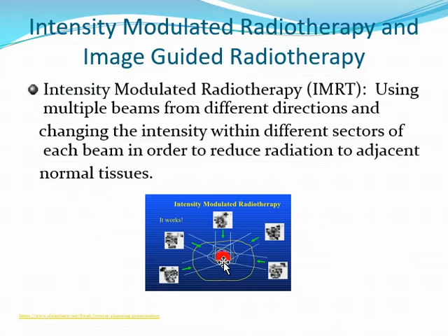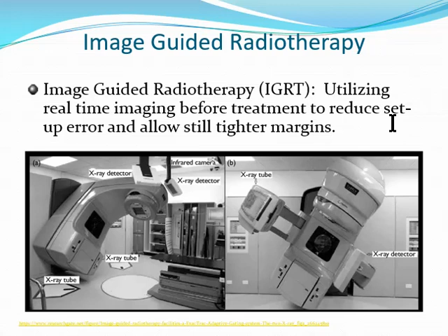For image guidance, our linear accelerators have X-ray imagers on the LINAC itself. So when the patient's in position to be treated, right before you turn the beam on, we can get either conventional X-rays or a limited CT scan. We call that a cone beam CT, which will give us confidence that the area we're treating is what we want to treat. That enables us to have tighter margins, so that way we're treating less normal tissue and hopefully causing less side effects.